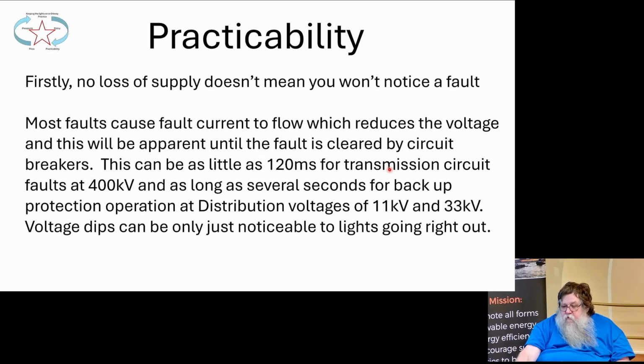So practicability, what does it mean? The first thing to note is that no loss of supply doesn't mean you won't notice a fault. Faults cause high amounts of current to flow, which blow fuses or break protection. That reduces the voltage. So when you see a fault, your lights dip. And you can sometimes see it in Orkney. You'll see your light dip for a moment and then come back again. And that dip in the lights is usually caused by fault current on another circuit. If the circuit that has got the fault on is your circuit, your power will go right off.